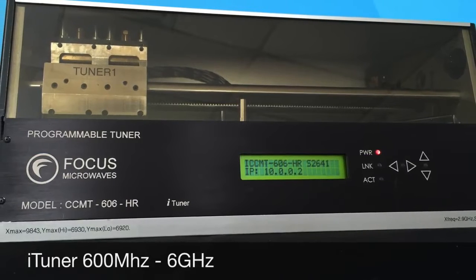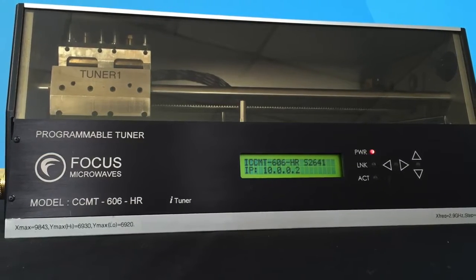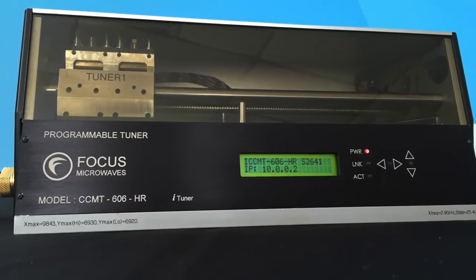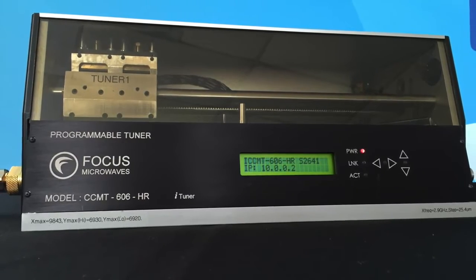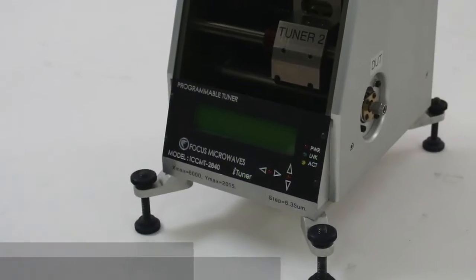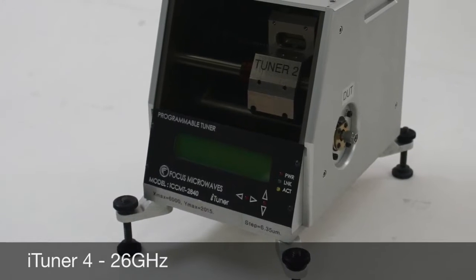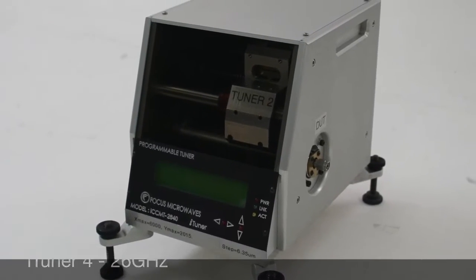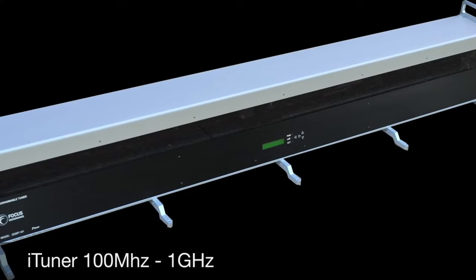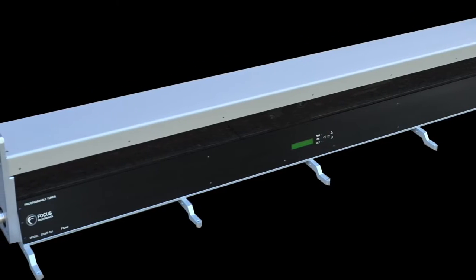All tuners are Ethernet controlled and have an onboard processor, memory, and firmware with interpolation and tuning capability, making it a fully standalone instrument. The iTuner series is optimized for broad bandwidth and high RF power. Each tuner contains 1 to 3 wideband probes which cover different frequency ranges for maximum tuning range.